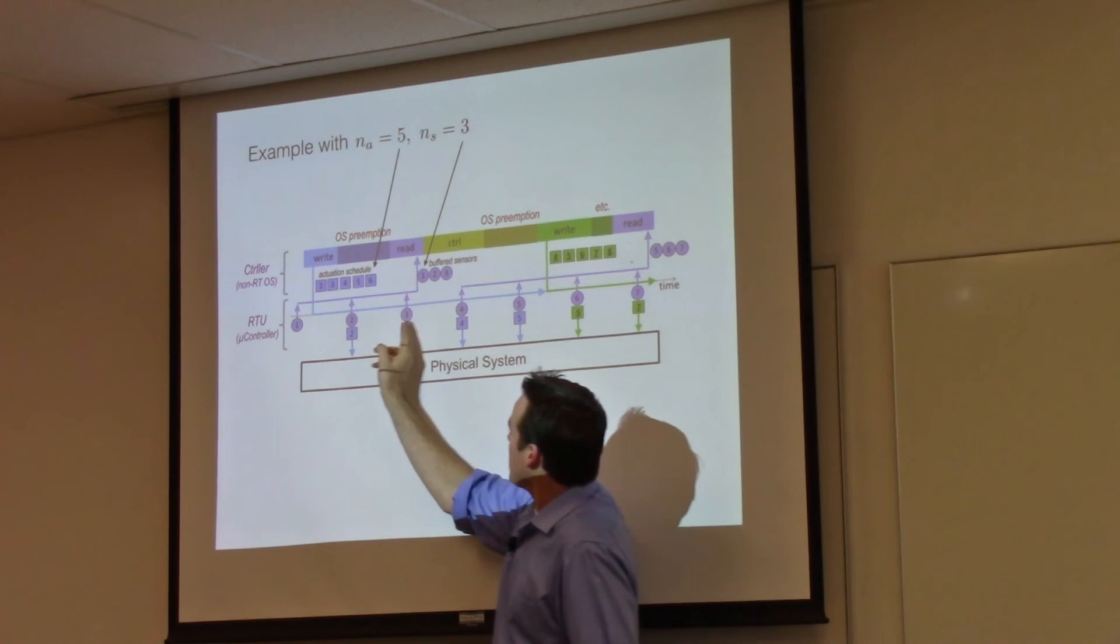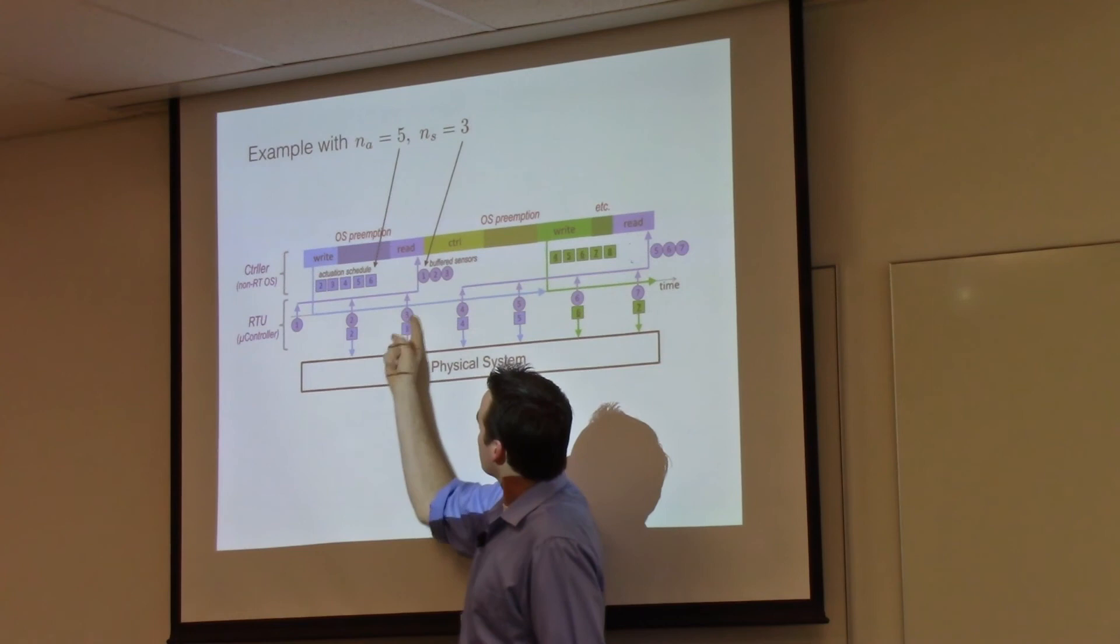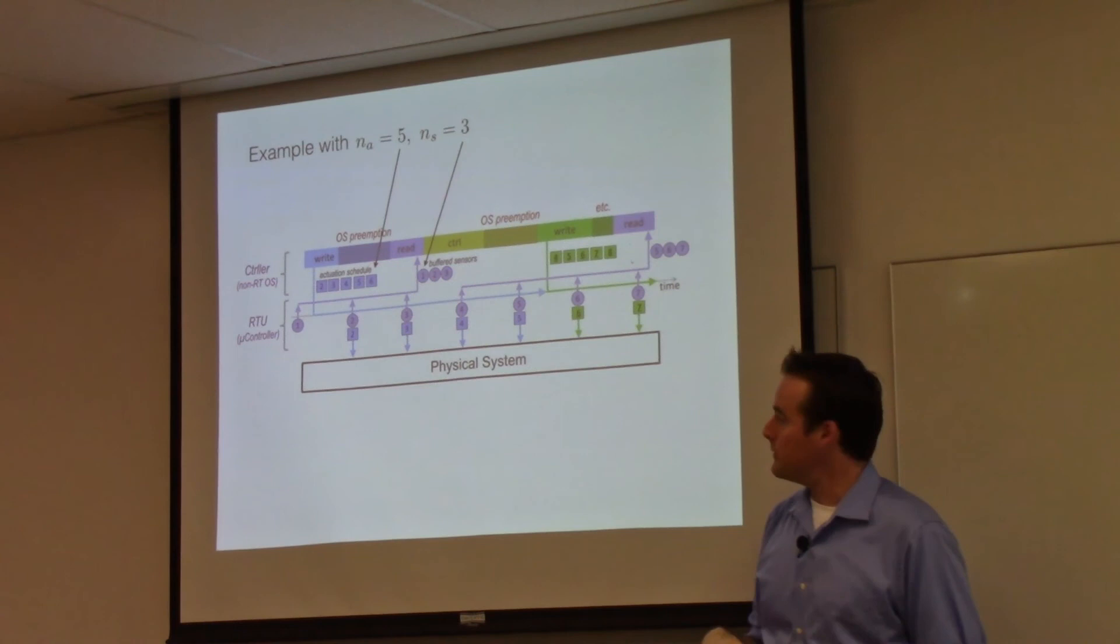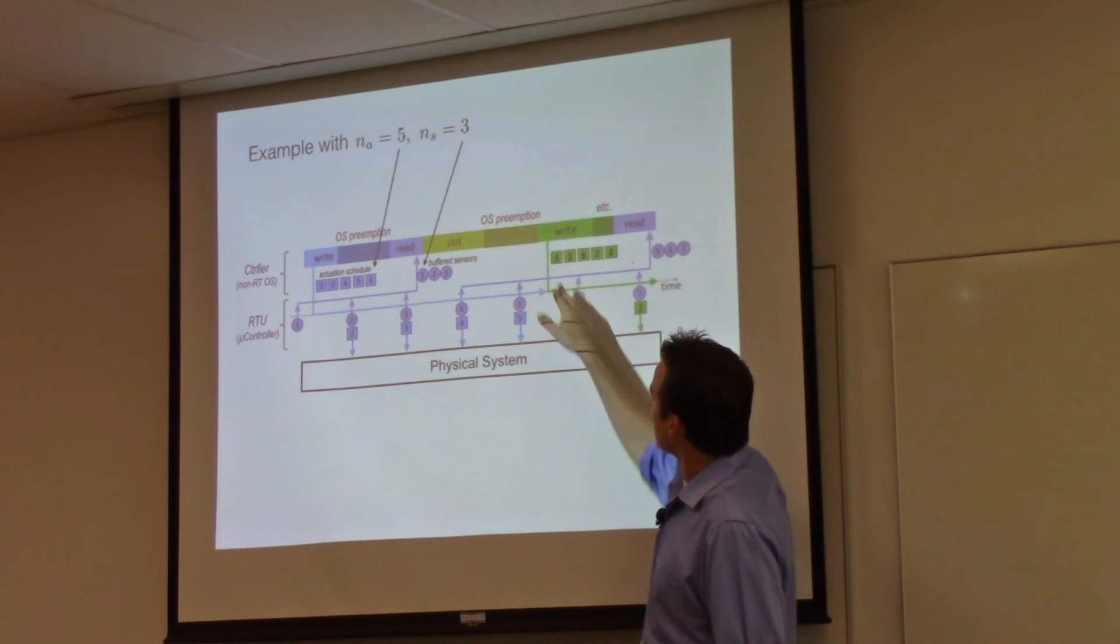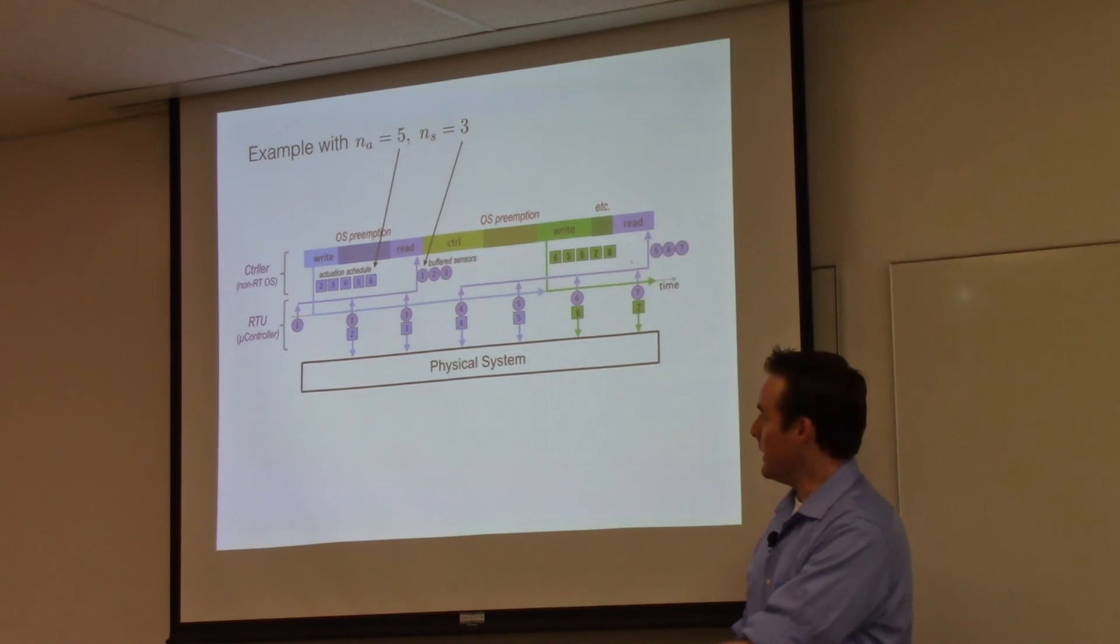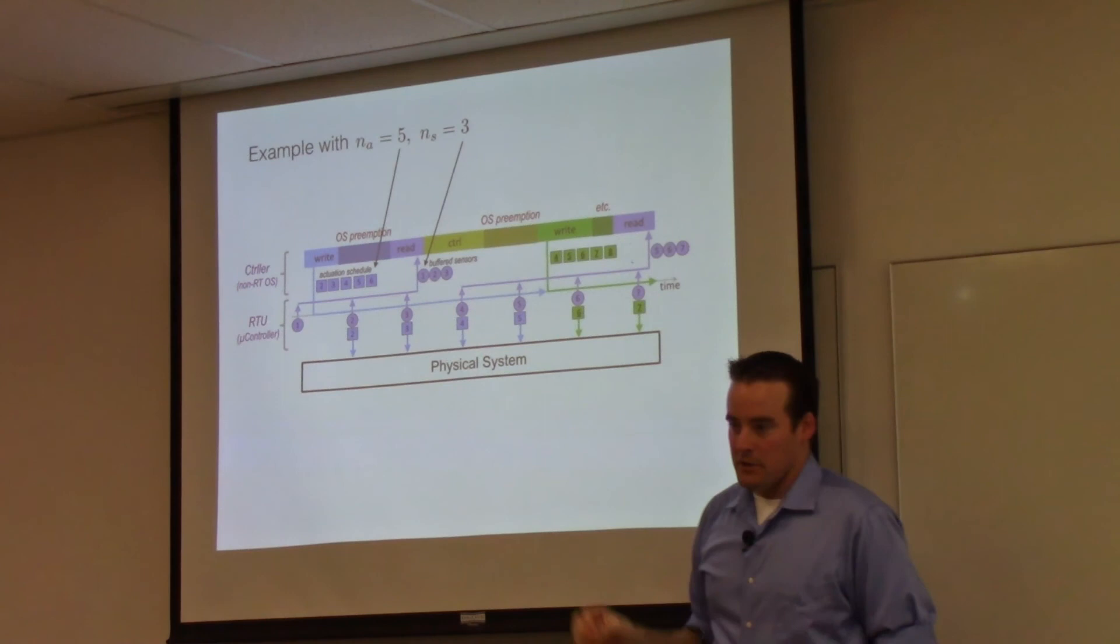In the meantime, the RTU is also sampling at very precise times, those purple circles. When the controller calls read, it gets to collect all of the buffered sensor values that it missed, that happened since the last time it called read. Then the controller gets to do the control. It might get preempted. At the end of the day, it has computed a new vector of actuator values to assign to the RTU. These are the green ones here. So it delivers them, and then the RTU takes it and runs with it.